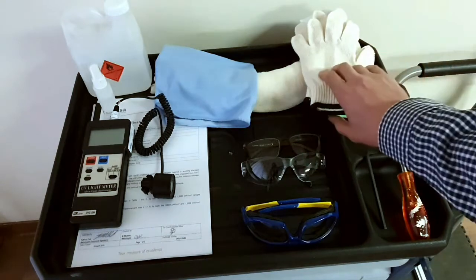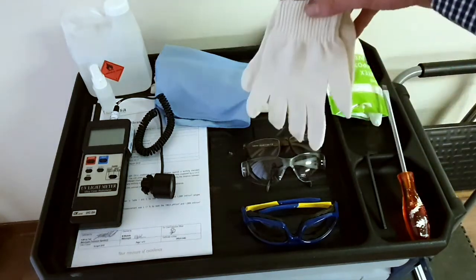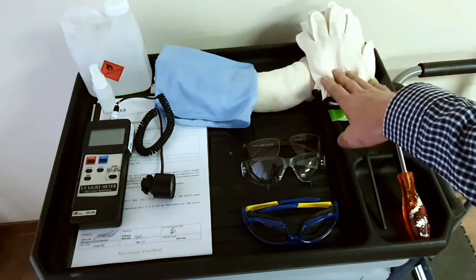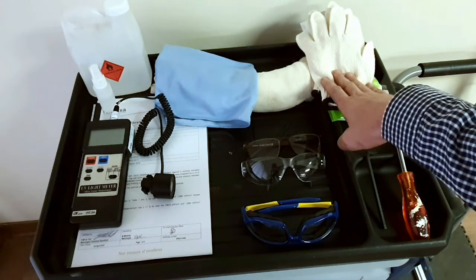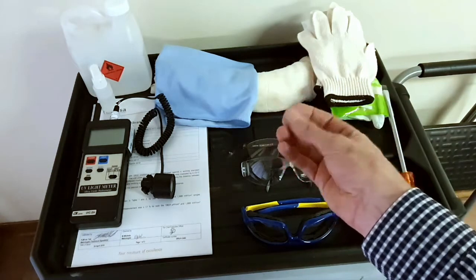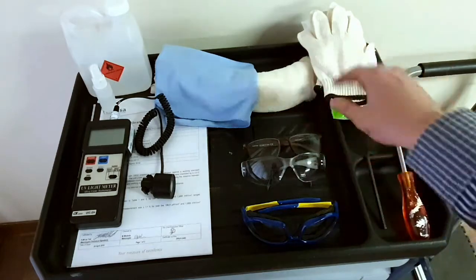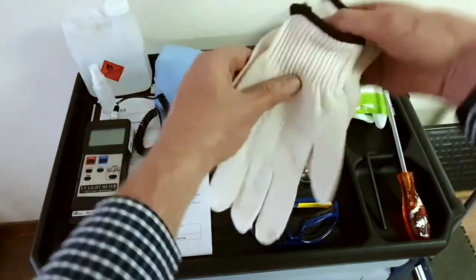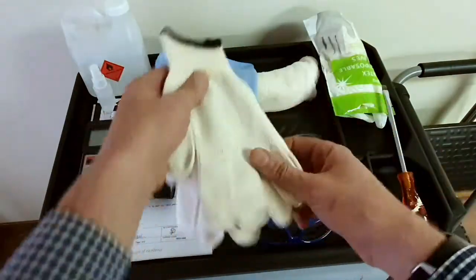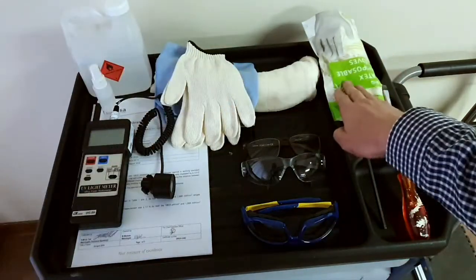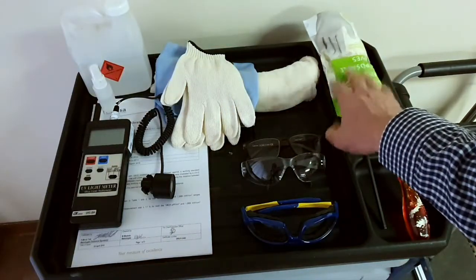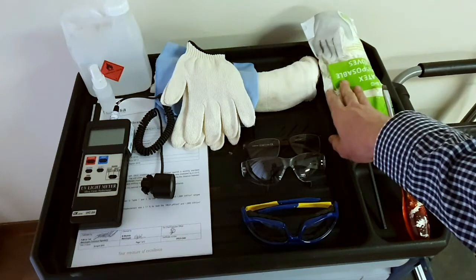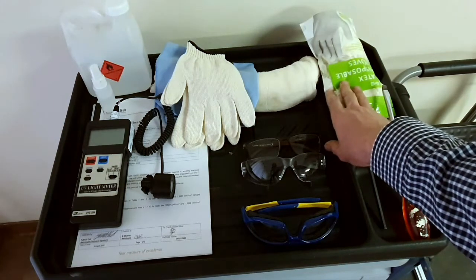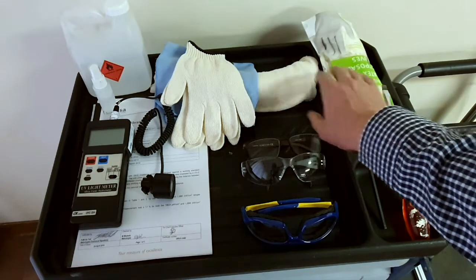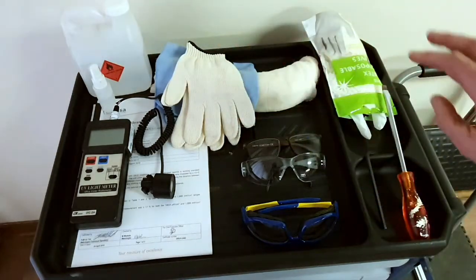All right. We also need gloves. Can't be touching any of the internals of the device with our bare hands. The oil in your fingers can leave residues on the lamps and reduce their efficiency. So just a pair of clean cotton gloves are more than appropriate. Don't use latex gloves or nitrile gloves or rubber gloves. These can also leave residues on the lamps, especially if the internals of the device are hot. So that's a much safer option.